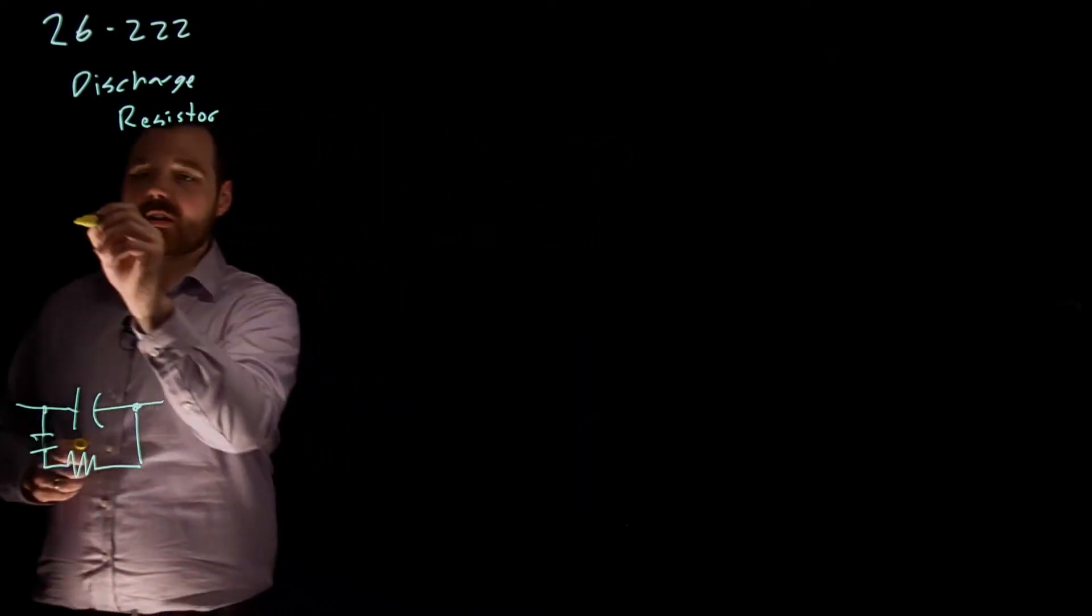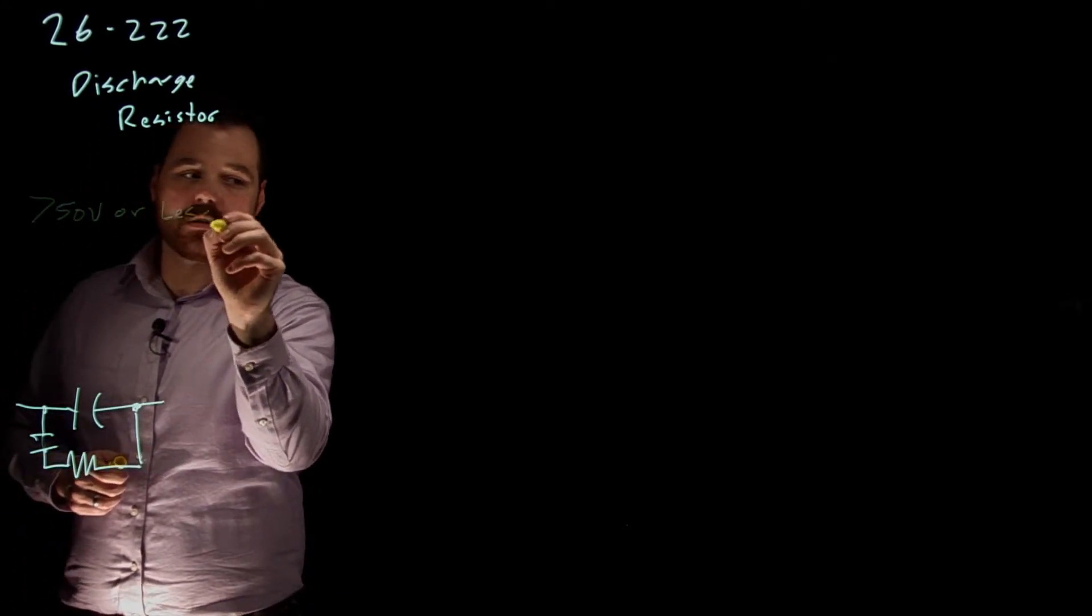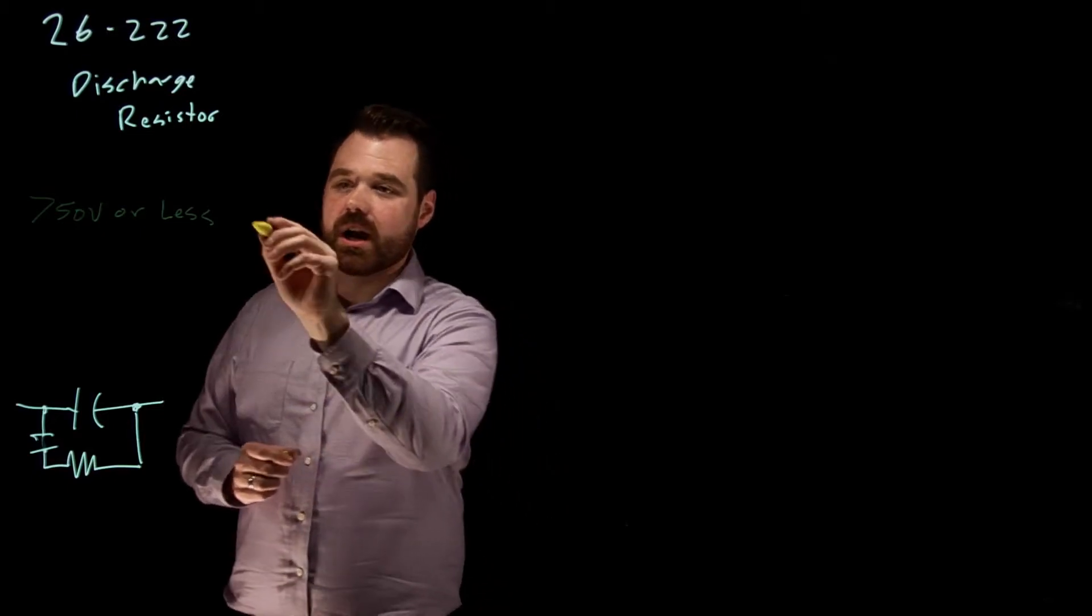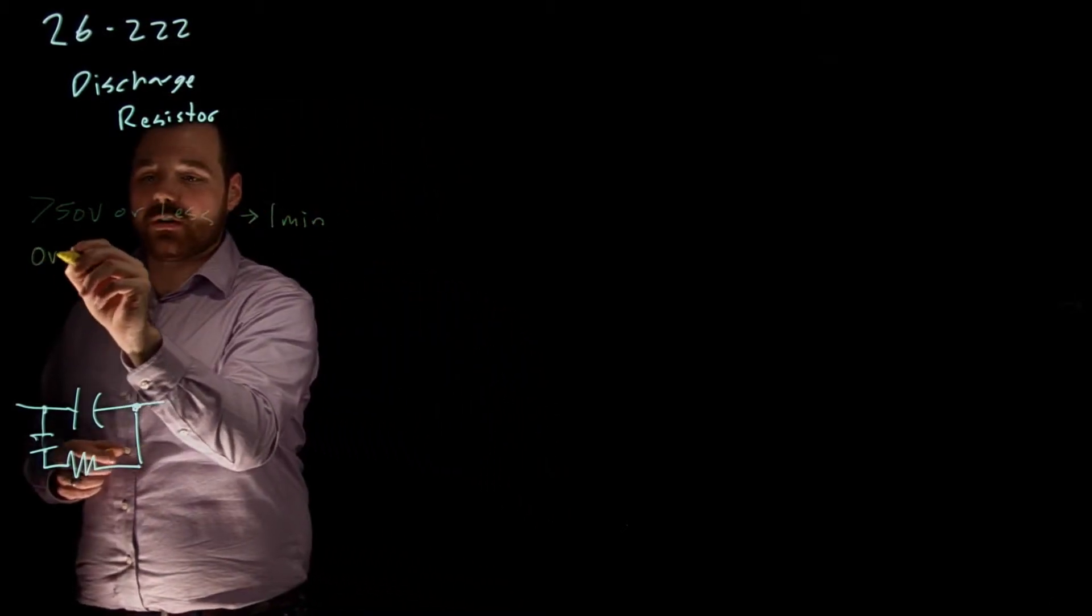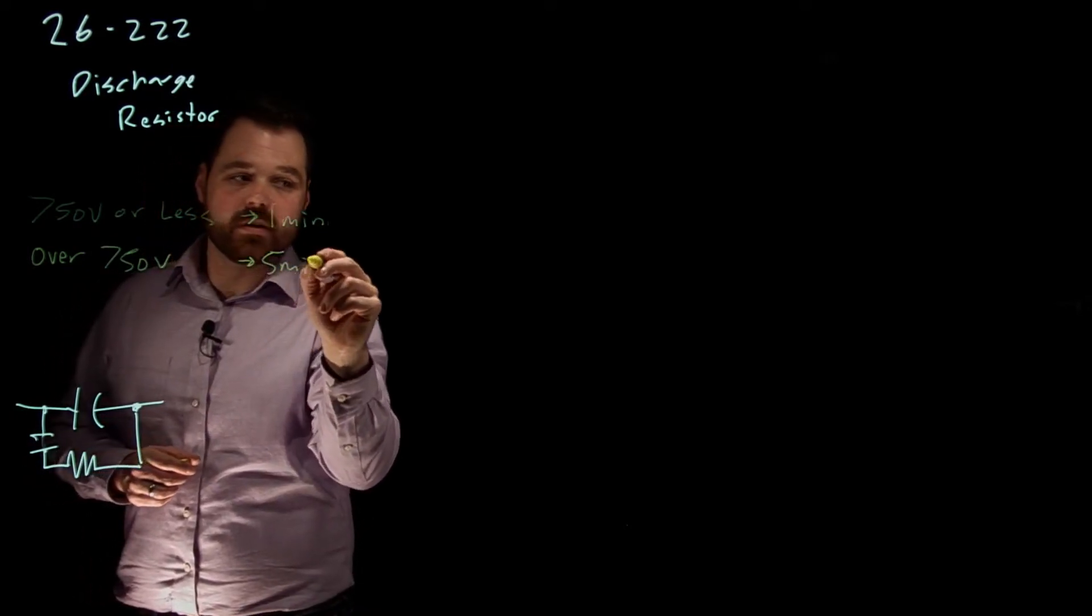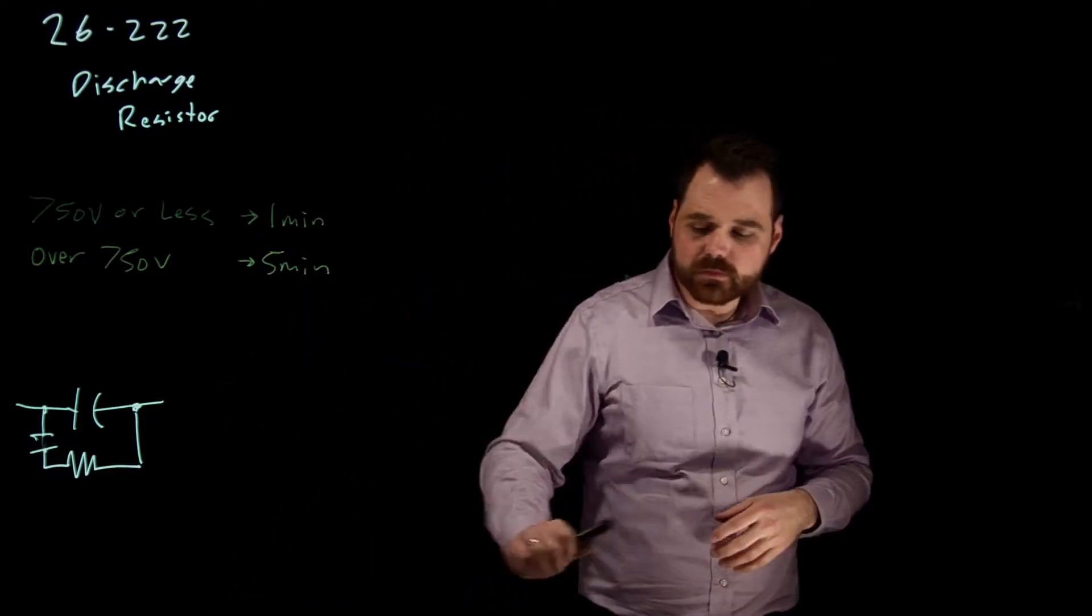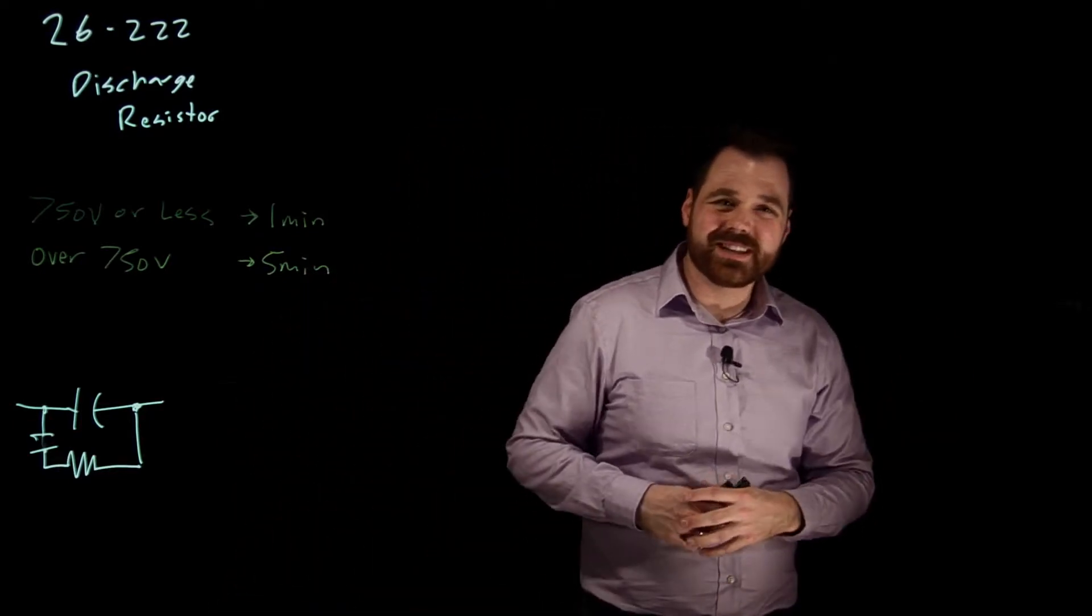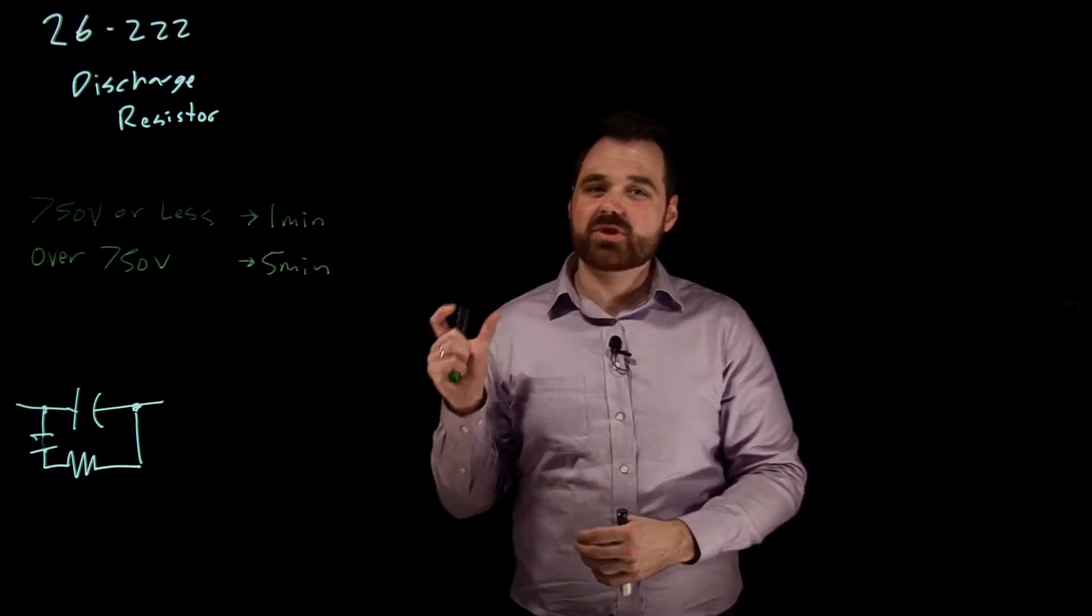Now we talked a little bit, if we are 750 volts or less, we would have one minute. If we are over 750 volts, we have five minutes in order to discharge that capacitor. So that would look a little bit something like this. When we de-energize a capacitor from a circuit, it's now storing a charge.